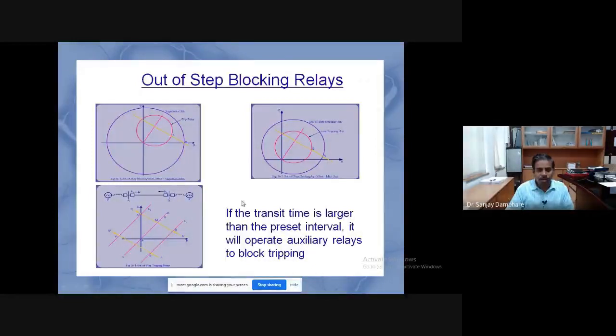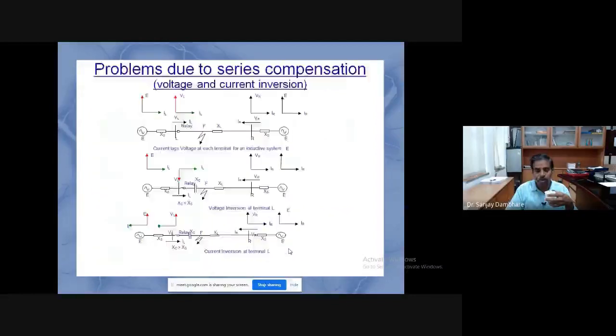On the contrary, for a fault, the travel time will be very small because fault is a fast phenomenon. As the travel time is small, the relay is put in an unblocked zone and is allowed to trip. This is how faults are distinguished from power swings.